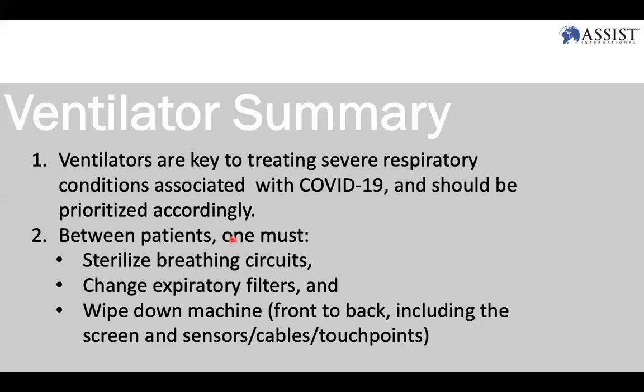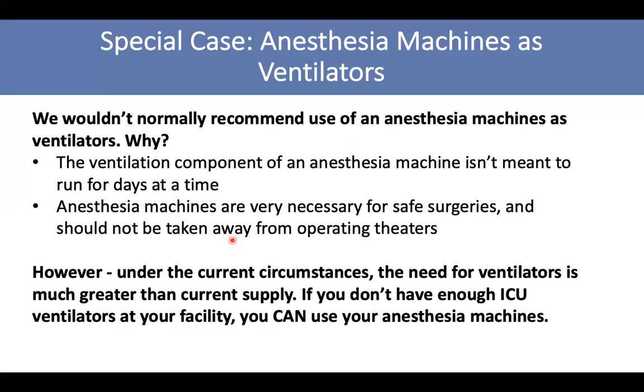Now for today's short discussion, we want to go through utilizing anesthesia machines as ventilators. There's a severe shortage of ventilators in most health systems. And with the COVID-19 pandemic, there's been a huge stress on the supply chain. And so people are considering and actually recommending the use of anesthesia machines as ventilators. Before we get there, we do want to say that normally we would not recommend the use of an anesthesia machine as a ventilator. Two of the key reasons are the ventilation component of an anesthesia machine isn't meant to run for days at a time. Usually, the anesthesia machine is designed to be reset and recalibrated every 24 hours. And some of these patients with COVID-19 end up being in ICU care for several weeks. And so it was not designed for that.